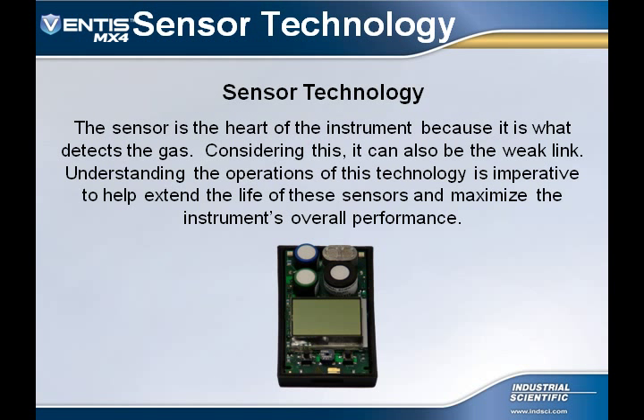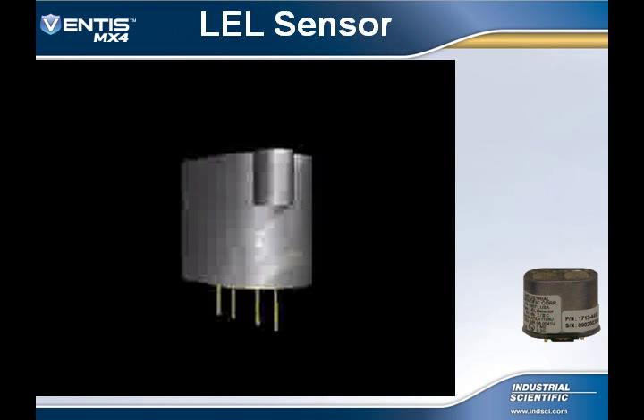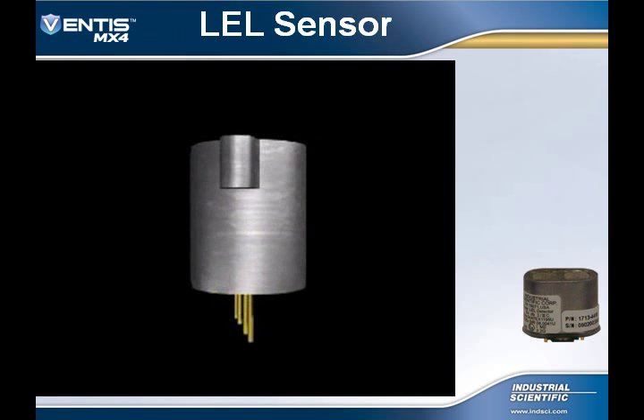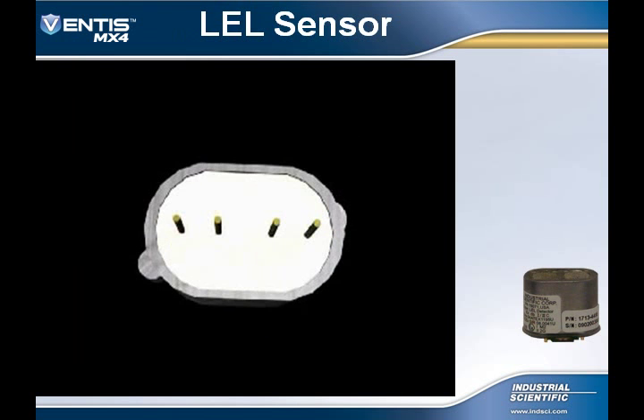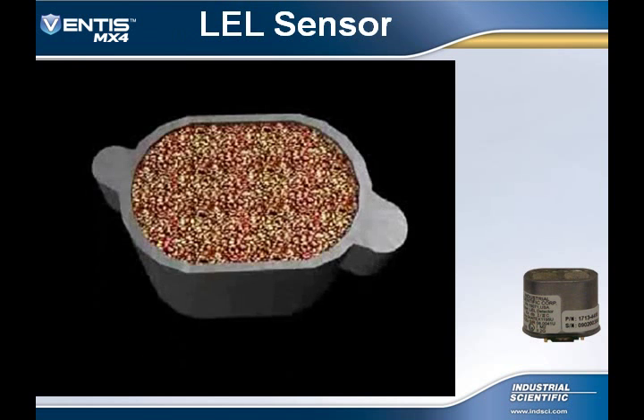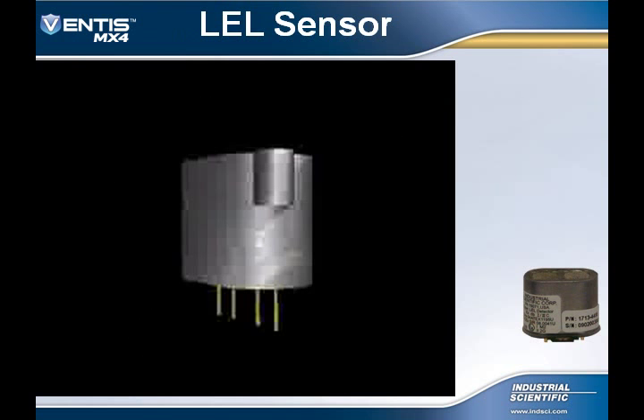The sensor is the heart of the instrument because it is what detects the gas. Considering this, it can also be the weak link. Understanding the operation of this technology is imperative to help extend the life of those sensors and maximize the instrument's overall performance. One of the sensor technologies that can be used in a Ventis MX4 is the catalytic diffusion sensor. It is used to detect combustible gases and displays them in % LEL, lower explosive limit.